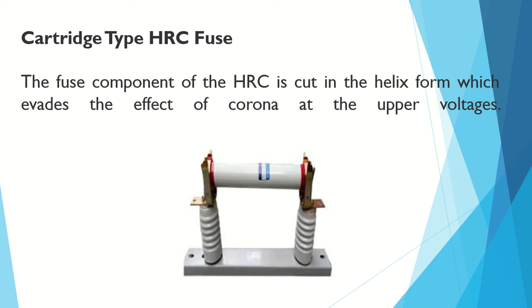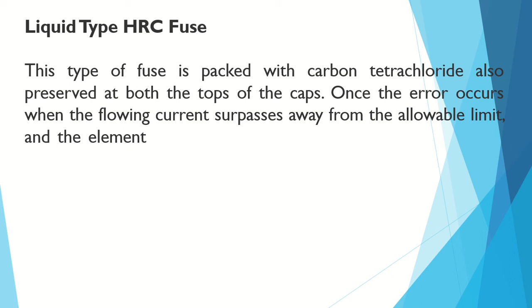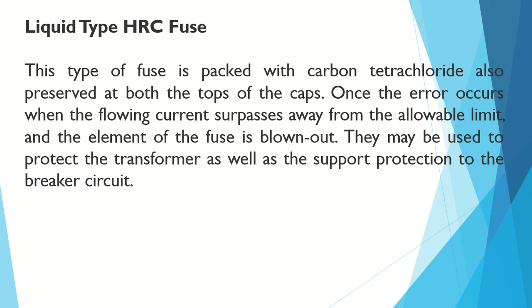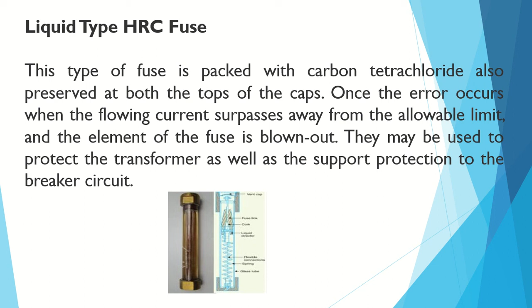Liquid type HRC fuse - this is also a high voltage fuse. This type is packed with carbon tetrachloride and sealed at both ends with caps. When a fault occurs and the flowing current surpasses the allowable limit, the element of the fuse blows out. They may be used to protect transformers as well as to provide support protection to the breaker circuit. This is an example of a liquid type HRC fuse.